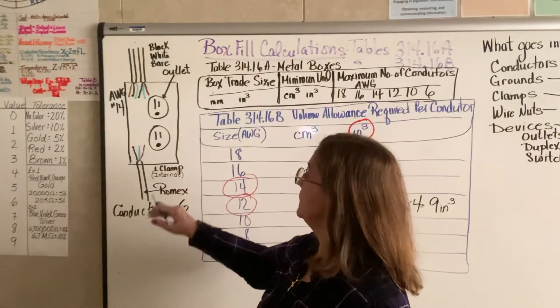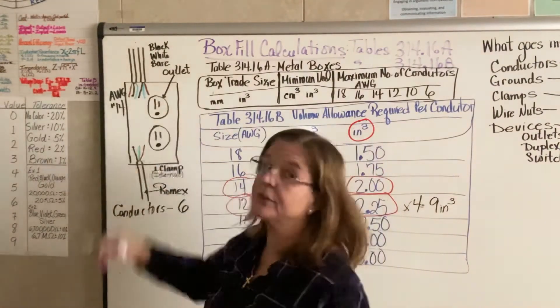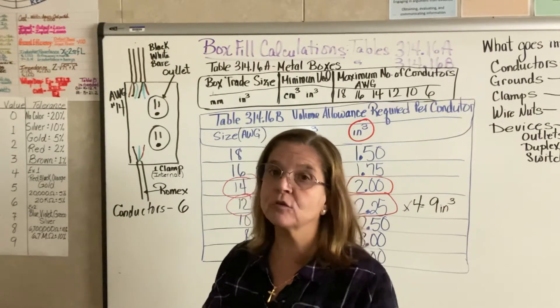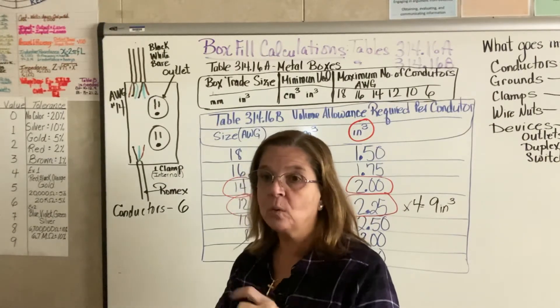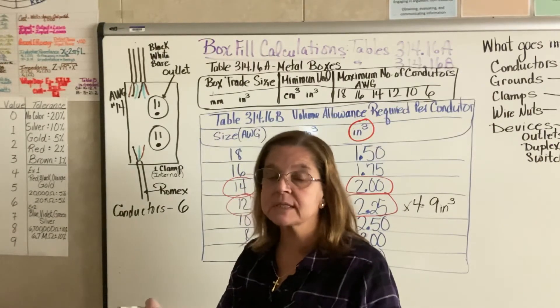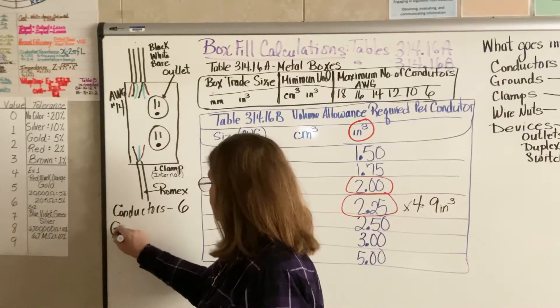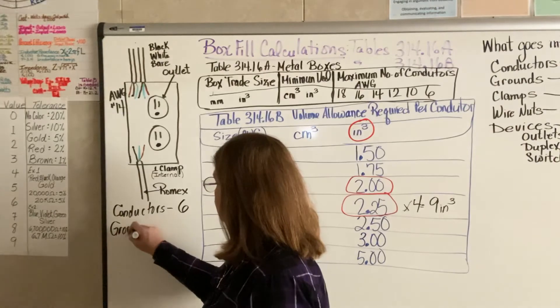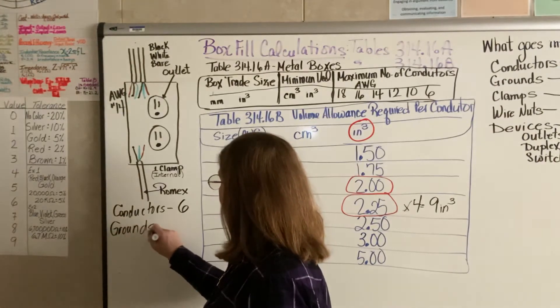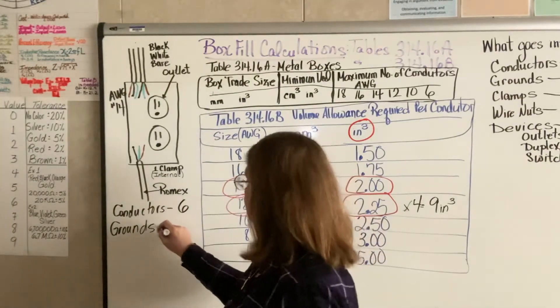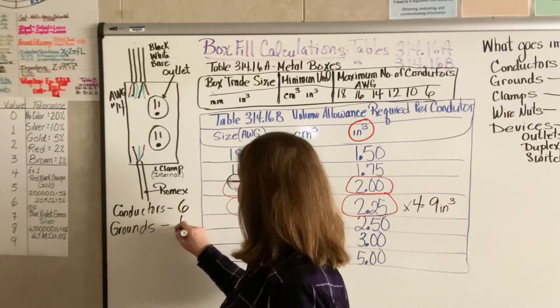Next thing I look at is, well, I do have the three grounds, but we only count the grounds once. You pick whatever is the largest AWG. So for the grounding wires, all together there's three, but we count it only once. So that's going to be one.